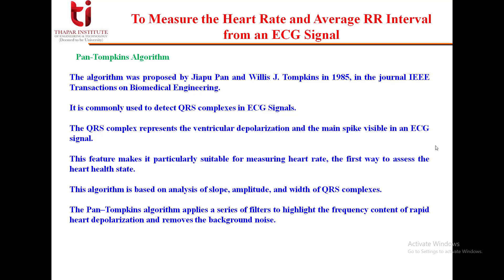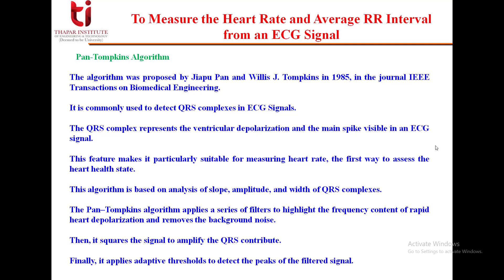The Pan-Tompkins algorithm applies a series of filters to highlight the frequency content of rapid heart depolarization and it also removes background noise. Finally, it squares the signal to amplify the QRS contribution and then applies an adaptive threshold to detect the peaks of the filtered signal. Previously we discussed a similar approach but used a constant threshold of one, whereas here we use an adaptive threshold.